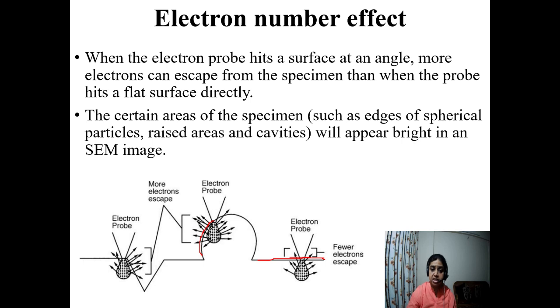But if you see the trajectory, a large number of secondary electrons are coming from the curved surface. So if your sample is hit on a surface, suppose at an angle, more electrons will escape from the specimen than from a flat sample. So it will be reflected in your topographical contrast. Whenever there is a sample where the electron beam hits at some angle, a large number of electrons will escape from the curved surfaces than from flat surfaces. This will create contrast in the number of electrons reaching the detector.